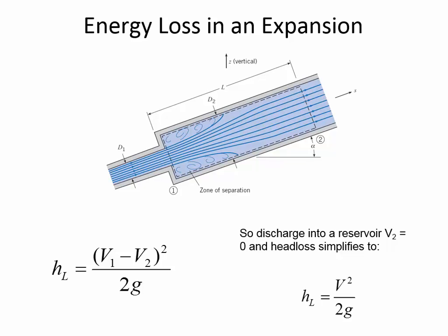But because of the energy losses, it would maybe say that the pressure increased only by 8 kPa. And so the difference between what you expected, that 10 kPa predicted by Bernoulli's, and the 8 kPa that you're measuring by the gauge, that's how much energy was lost due to the fitting itself.